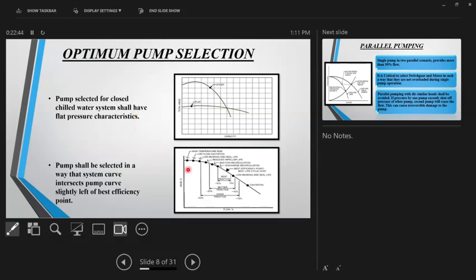Another thing is, you can see the pump curve starts from this point all the way to here. So theoretically, you could select the operating point anywhere in between, right? If there is no other problem, I can select the pump here, or here, or here, anywhere. But then again, the recommendation of AECOM is don't select on the extreme right-hand side, nor on the extreme left-hand side.